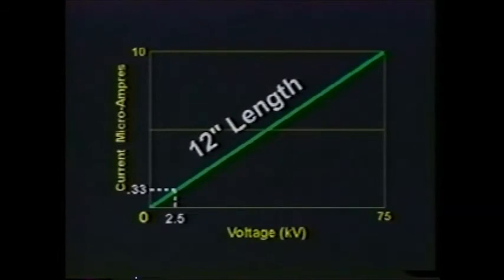The wet test is similar to the dry test except that the full scale value is 75 kV instead of 100 kV. Calculating the same correcting values, we get a correcting factor of 30 for the voltage correction and the same factor of one half for the length resulting in an actual amplification factor of 15.